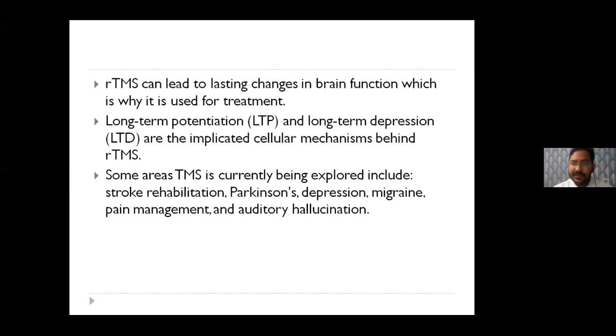What does the TMS device look like? I showed the picture earlier. A TMS stimulator is the size of a mini fridge and has a power cable. It will have various controls on it to adjust the stimulation parameters such as the pulse intensity, number of pulses and the pulse frequency. The coil looks like one or more loops, for example the figure of 8 coil that I showed earlier. You have a cable connecting the coil to the stimulator. The coil is held over the head, as part of the stimulator, by the hand of the operator or by a mechanical arm.